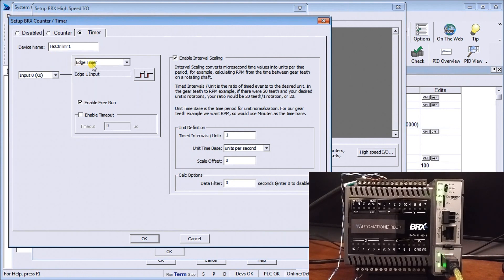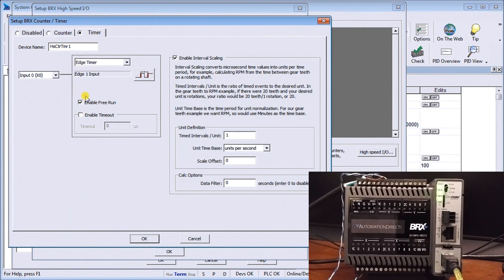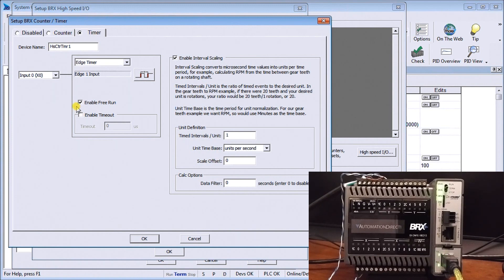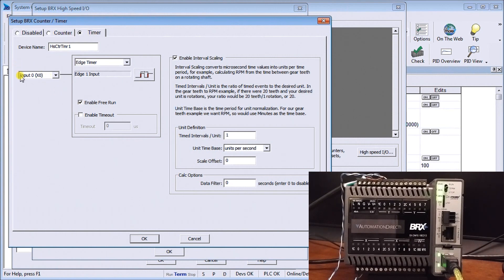So we have that set for a timer, it automatically will give it a device name, in our case here it's HSCTR TMR one or high speed counter timer one. And what we're going to do is call it on the edge timer so it matches the edge to edge, we will enable the free run so that means when we enable it the first time it will continuously run and give us the output and we're going to use input zero for that timer.